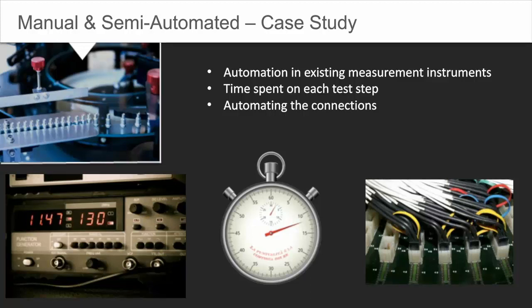Since the connections to the test points were manual, we recommended that they install a foot switch that the operators could press when ready to take the measurement. The test sequencer would then automatically advance to the next step. So it made the operations much easier. They would have to manually make the connections, but they could use their foot switch to automatically get the instrument to take the measurement and record it.